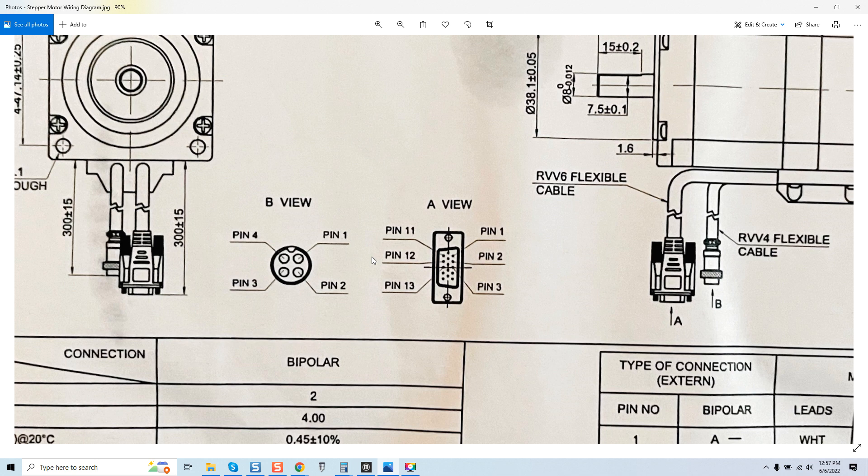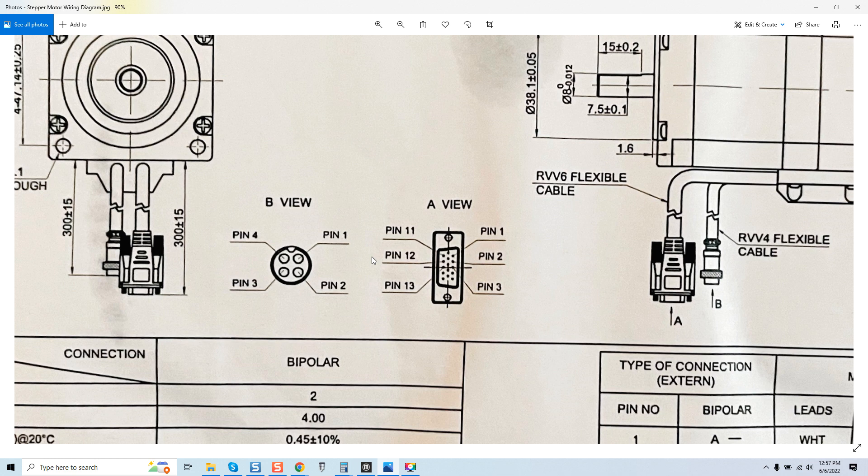Seems to be a misconception online that because it's a closed loop automation system that it does not require shielding or minimal shielding. It doesn't work that way. Double shielded cable is required for EMI to be mitigated in terms of this automation control system you're building.